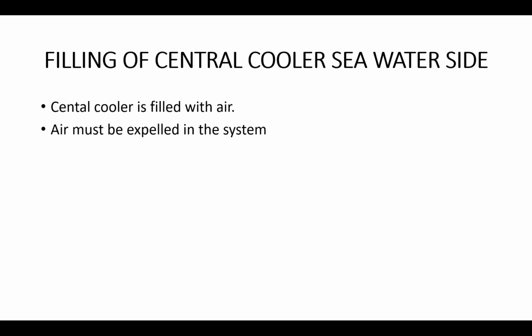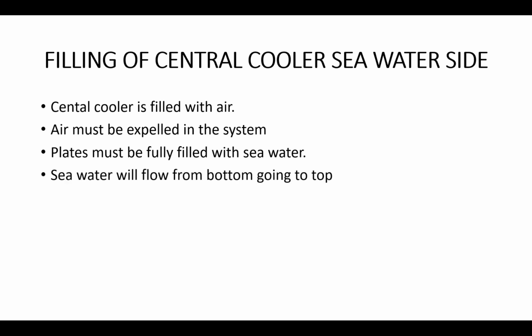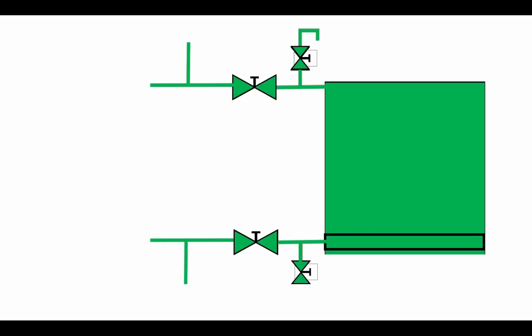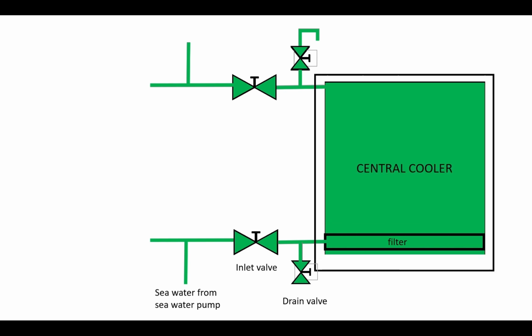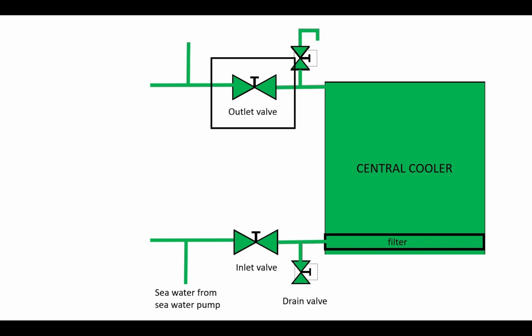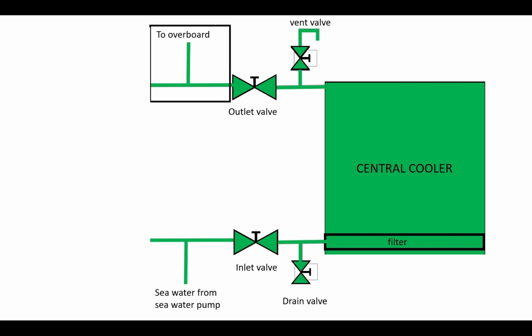Filling of the central cooler on the seawater side. First, the central cooler is filled with air, which must be expelled from the system. The central cooler plates will be filled with seawater from bottom going up while expelling the air. Seawater is transported from the seawater pumps. Seawater inlet valve. Seawater drain valve. Central cooler seawater filter. Central cooler. Seawater outlet valve. Seawater vent valve. Seawater going overboard.